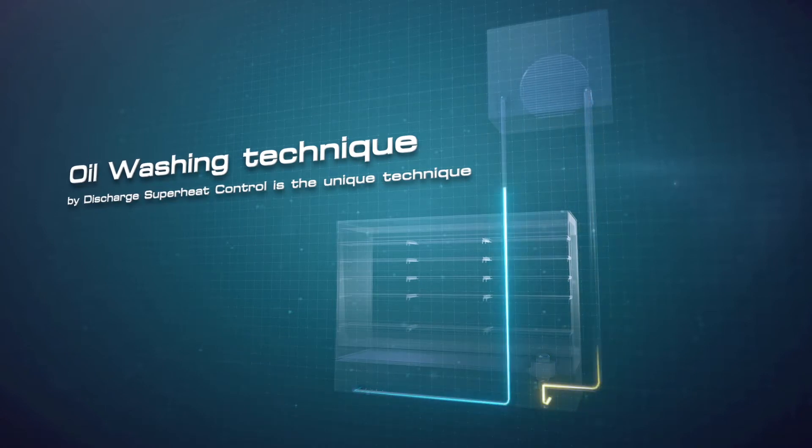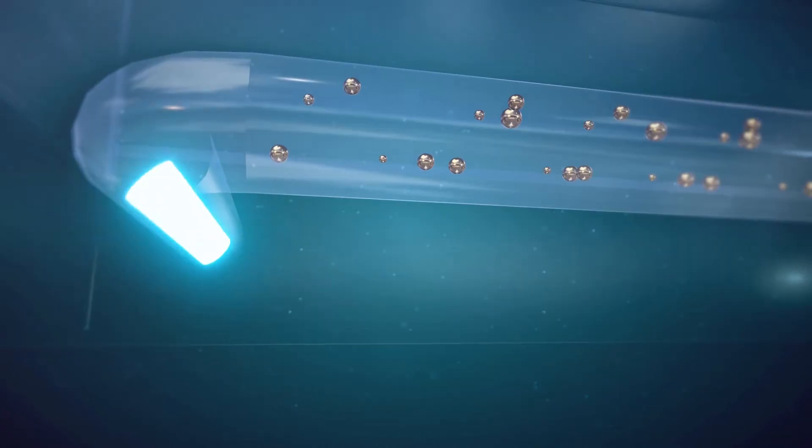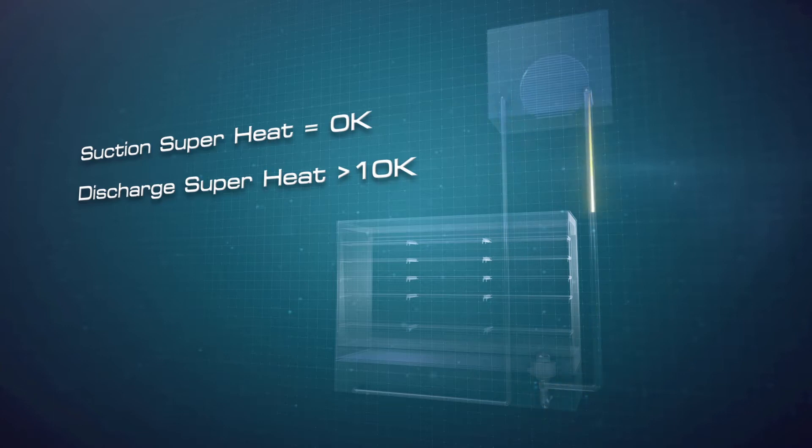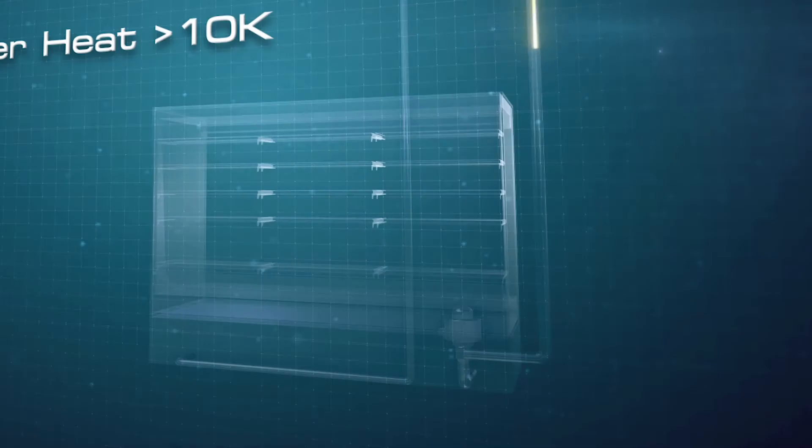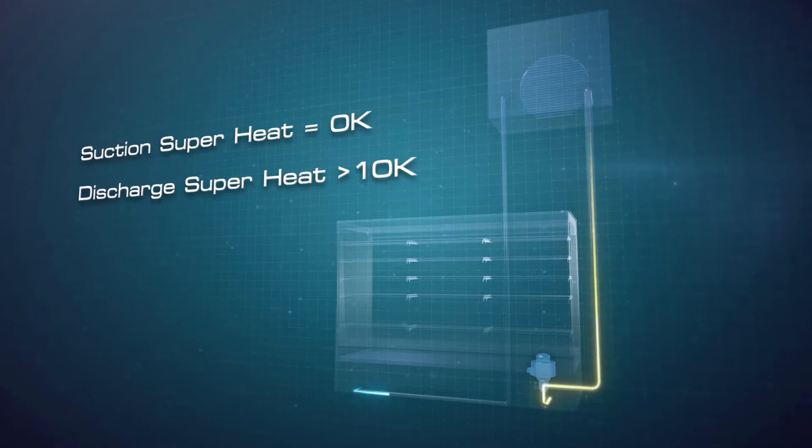During the oil washing process, the refrigerant will be partially condensed from gaseous to liquid by controlling the suction superheat to zero and discharge superheat to higher than 10 Kelvin. EEV valve openings are regulated evaporator by evaporator in a timely manner to return the oil to the compressor.